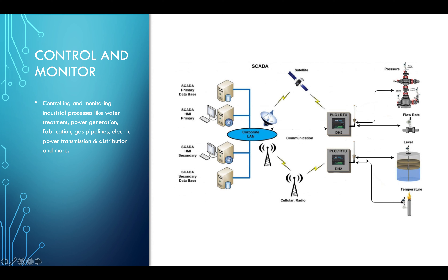The arrow is bidirectional because it handles both monitoring and control. For example, if we're monitoring the temperature and it's too high, we can lower the level in the container or lower the pressure in the tubes. The RTU also performs data acquisition — it samples analog devices, converts analog signals to digital via an A-to-D converter, and sends data back over the network. This supports controlling and monitoring of industrial processes like water treatment, power generation, gas pipelines, and electric power transmission and distribution.